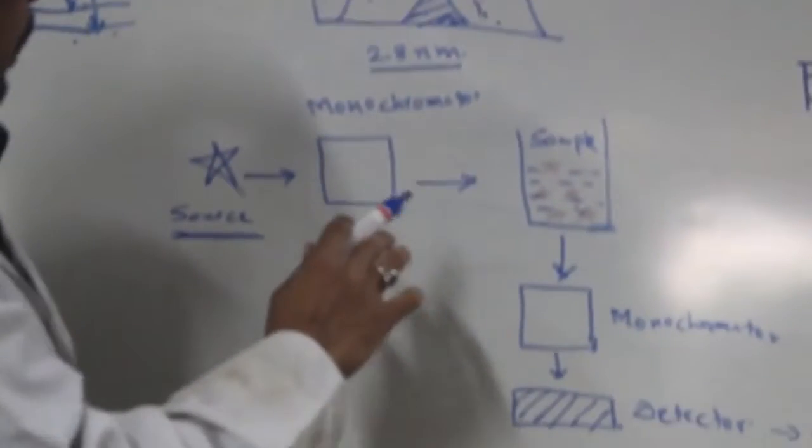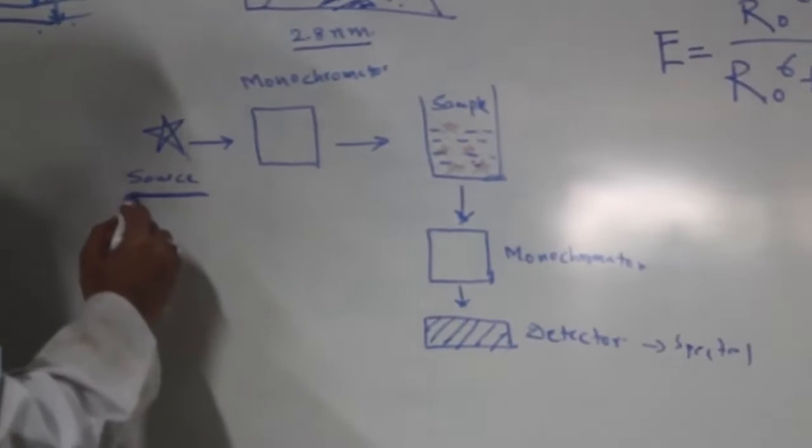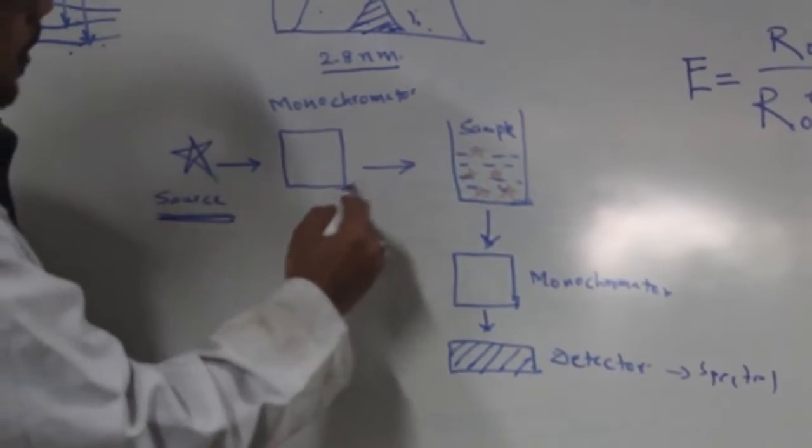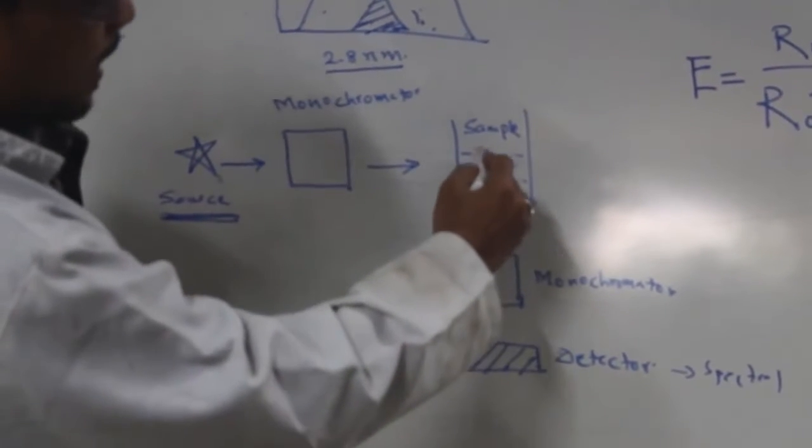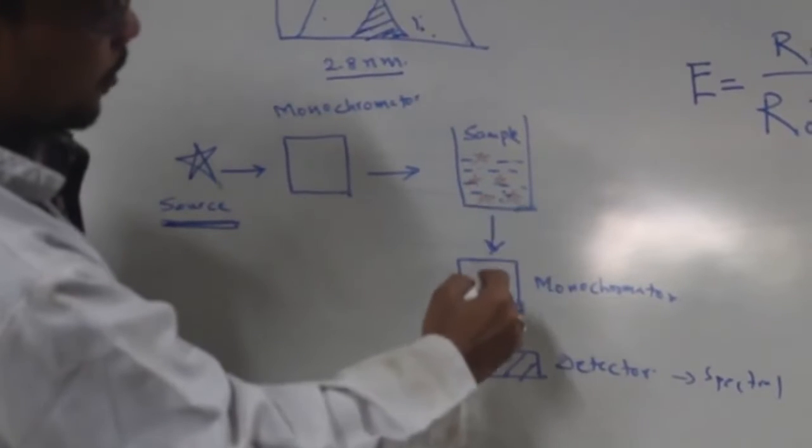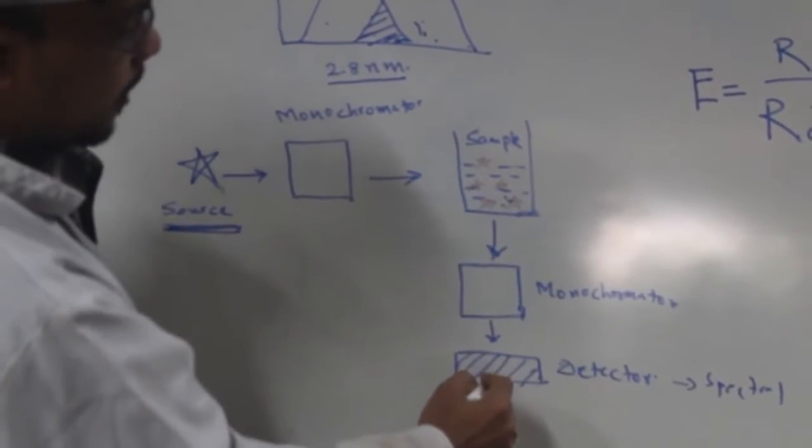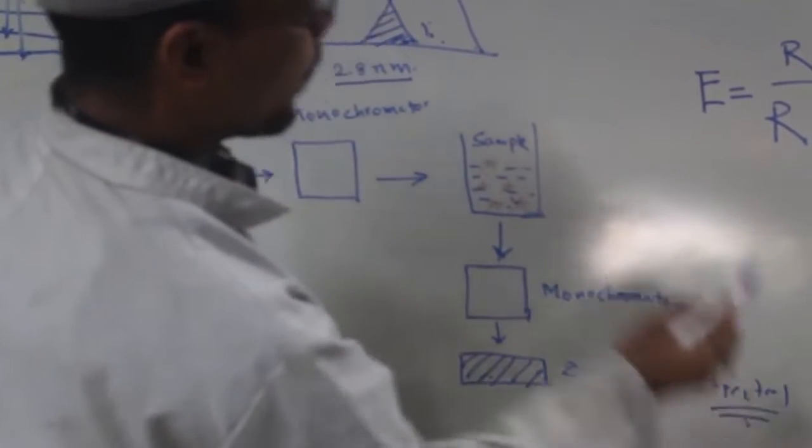To go into fluorescence instrumentation a little bit, you have a light source which passes through a monochromator and excites the sample. When the sample emits, that emission is collected through another monochromator and detected, giving the spectral output.